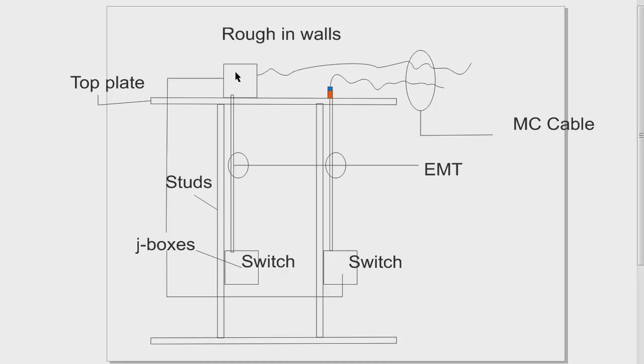That's good if you have multiple runs of MC going in there or home run, another EMT home run of wire. But if you just have one MC that you need to take down to your switch without having to make up a J-box and mount that all up and above you can use the EMT to MC connector.